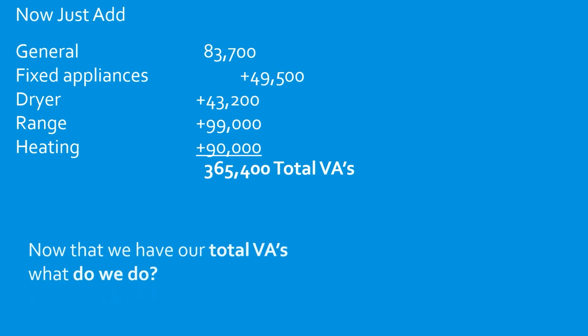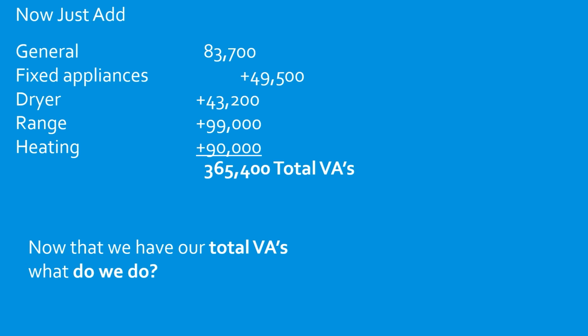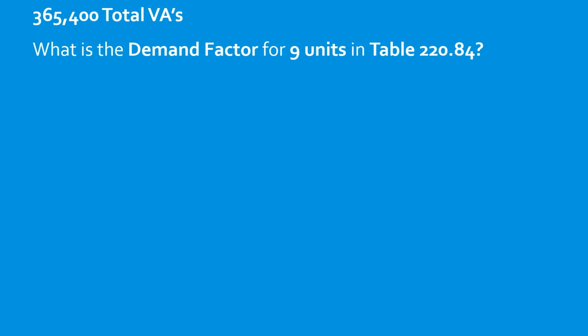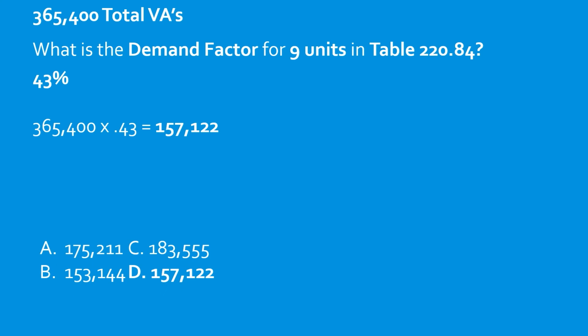So we take our total. After we have our total VAs, what do we always do? We always check for demand factors. Okay, so that's our total. What's the demand factor for 9 units if you go to Table 220.84? Okay, go ahead and take a minute, look there now, see if you can find it. 43%. So we just take our total, multiply it by 0.43. That is going to give us 157,122 VAs. And you select D.